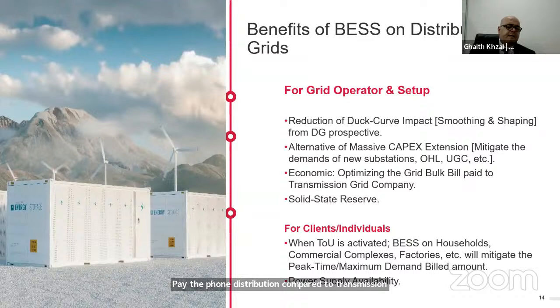However, regarding the battery energy storage system, we need to remember that it is the modern alternative to the so-called spinning reserve, which comes from rotary power plants or fossil fuel power plants. Batteries are a solid state reserve, and they have a faster response time and sit nearest to the load when it comes to distribution.